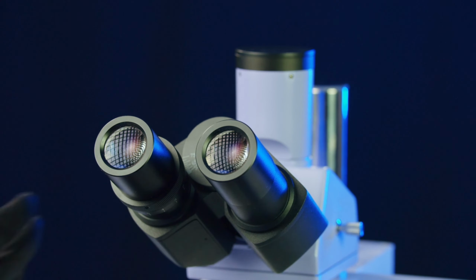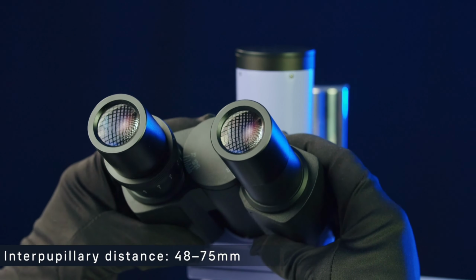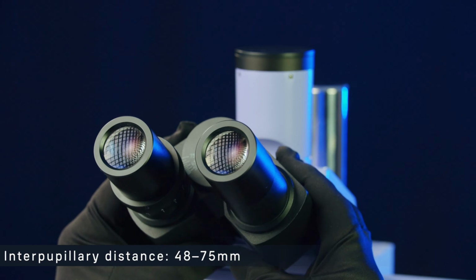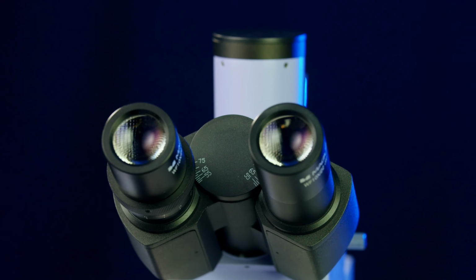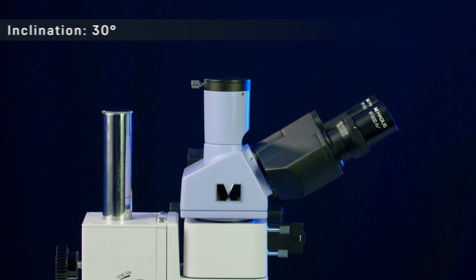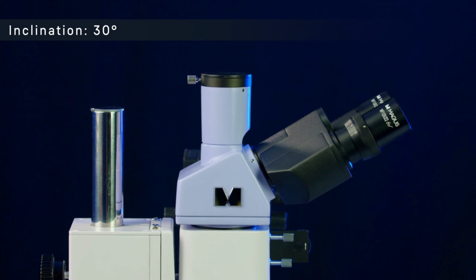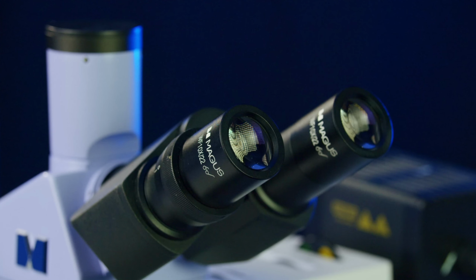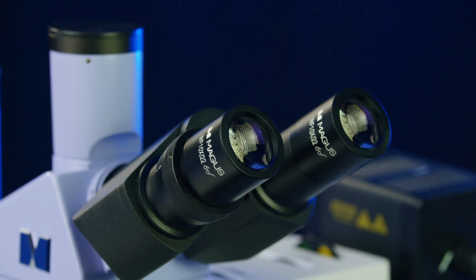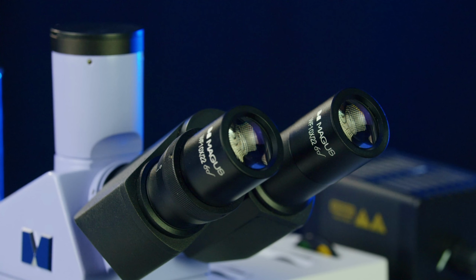Visual head and eyepieces. The visual head is trinocular. The interpupillary distance can be adjusted from 48 to 75 millimeters. The distance value is read off the scale. The inclination angle is 30 degrees. The standard package includes 10 times eyepieces with a field of view of 22 millimeters, featuring long eye relief for comfortable use both with and without glasses.